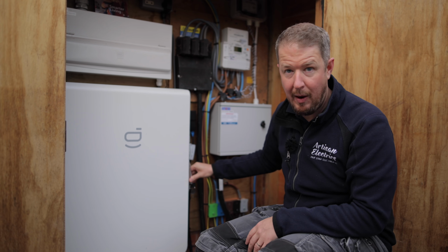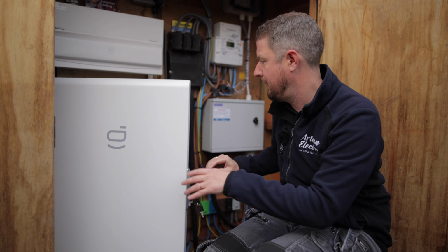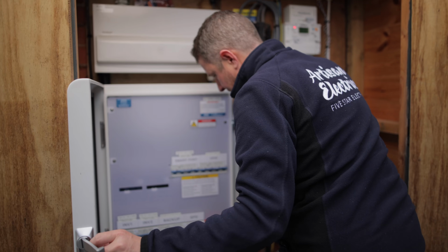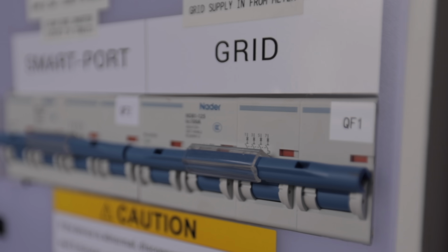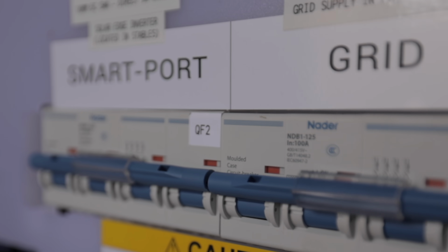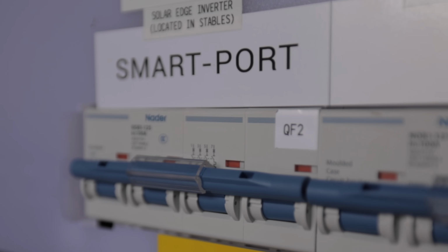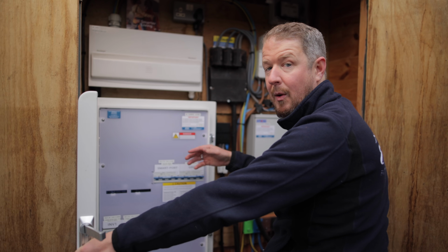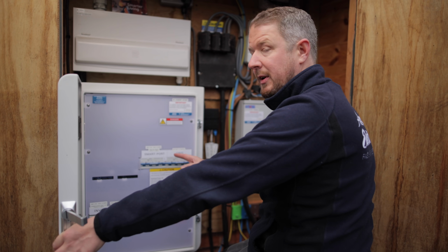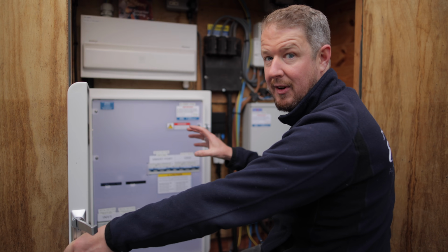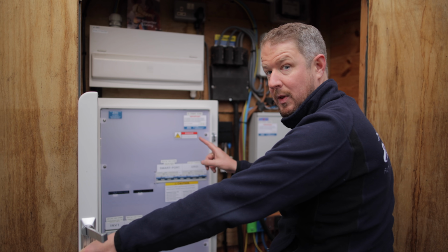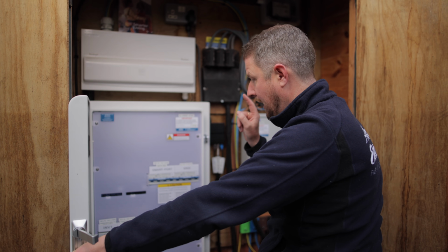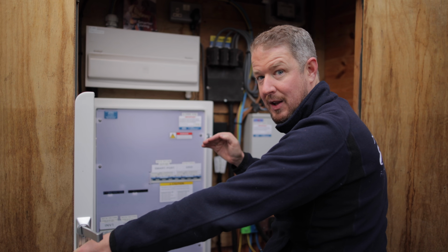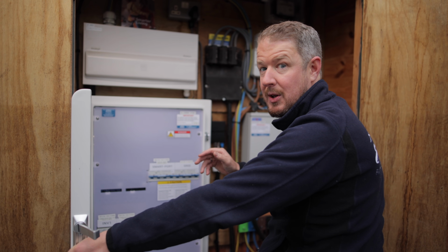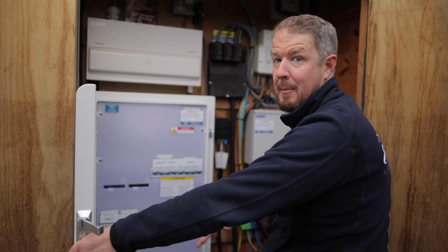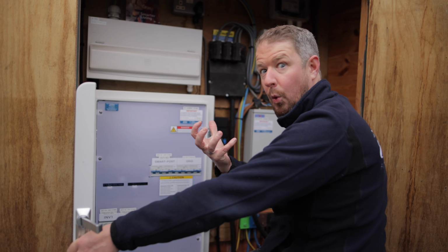So how does this work, you might wonder? Let's have a little look inside. Essentially what we've got here is our main feed from the grid in. Then we've got our smart port, which we've connected our SolarEdge inverter to. That means the SolarEdge inverter is monitored by the Sigenergy system, and we can see how much power is coming in from the solar. It also means that in an off-grid situation, the SolarEdge inverter is still going to work. And with a new software update that Sigenergy have just released, it will now ramp the inverter down using a change in frequency, to be able to stop the inverter from generating if the batteries are full and the house loads are not enough to take all of that 30 kilowatts.